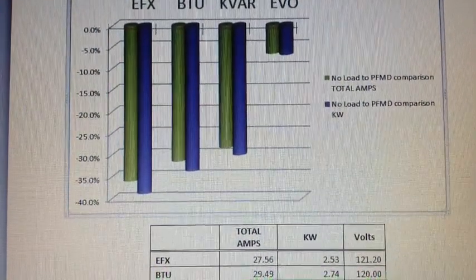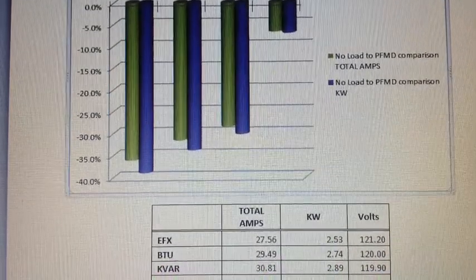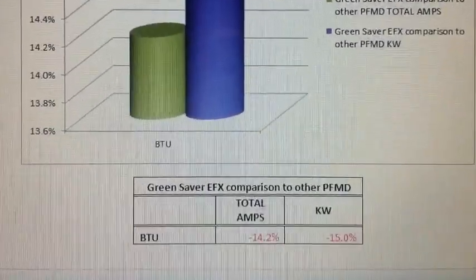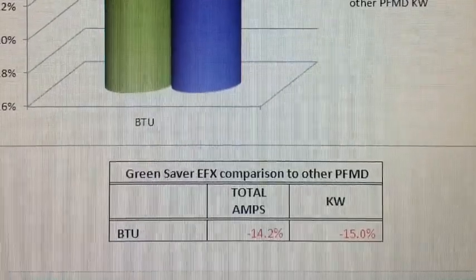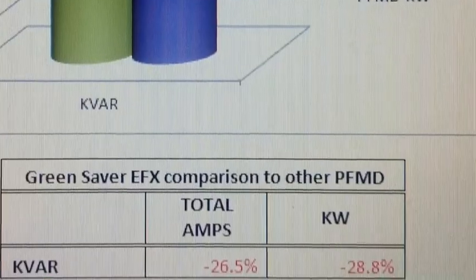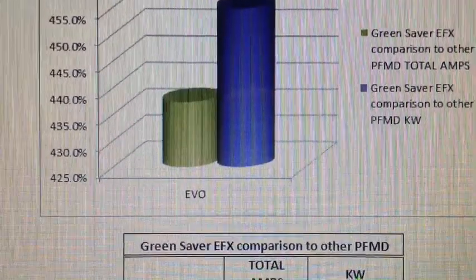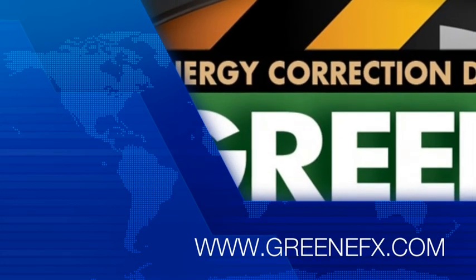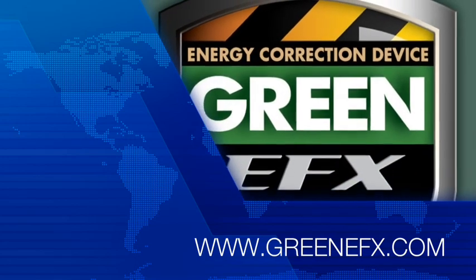All the power factor modification devices had a positive result in our test. The most positive was the Green EFX box, which actually provided a 38.9% reduction in kilowatts used. The Green EFX device outperformed the BTU device by 15%, the KVAR device by 28.8%, and the Green Revolution device by 455.2%. That is the end of our presentation showing that a power factor modification device is effective, and also demonstrating that the Green EFX power factor modification device is the most effective device.